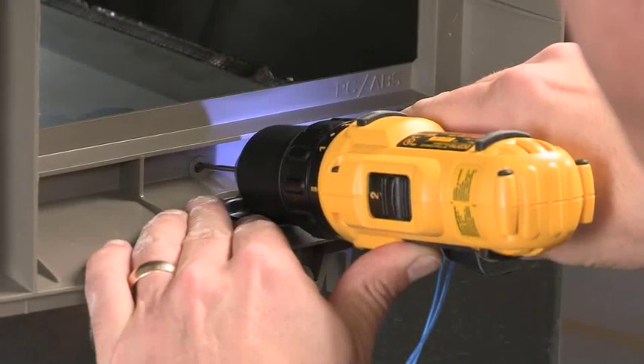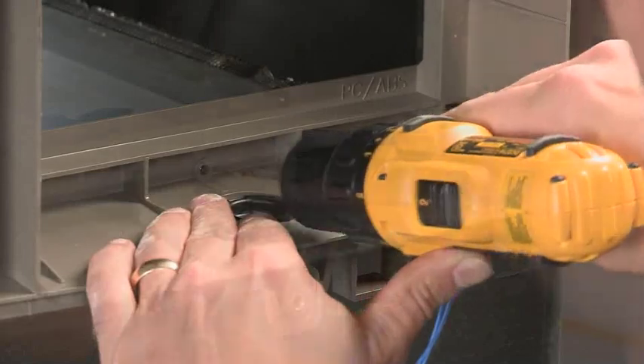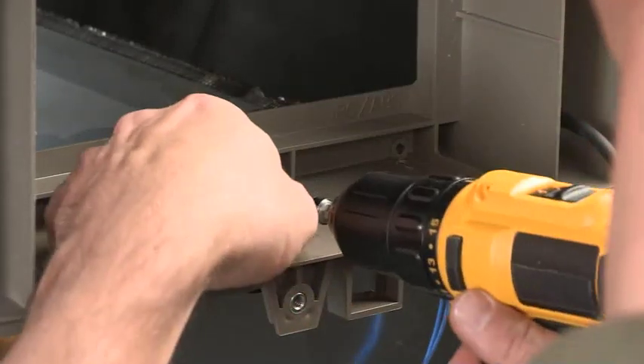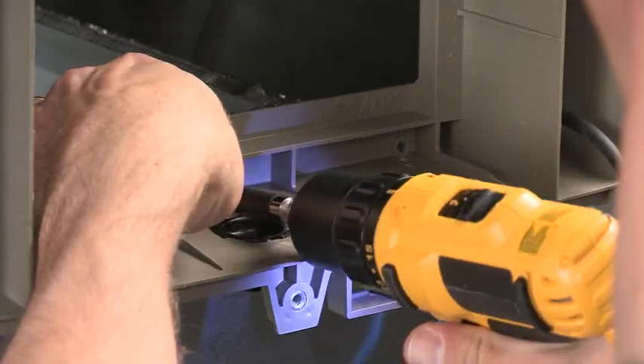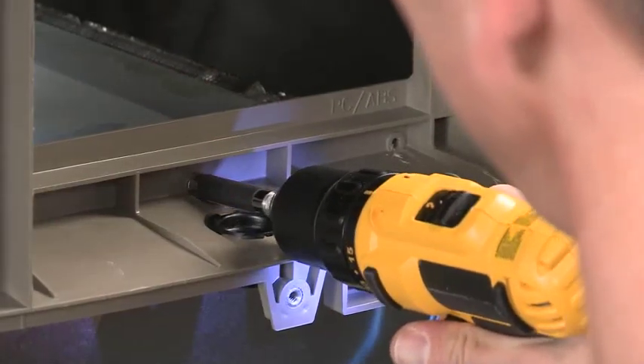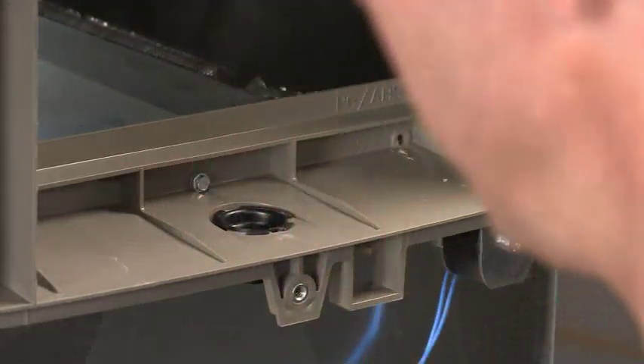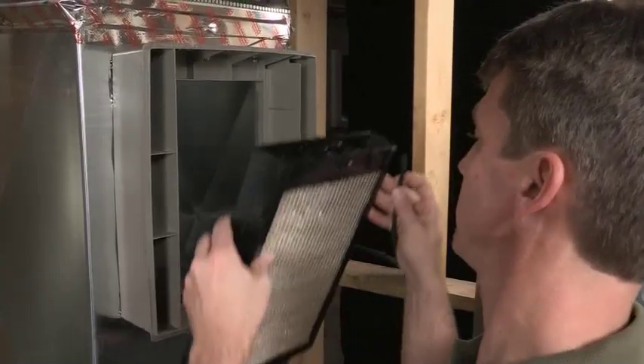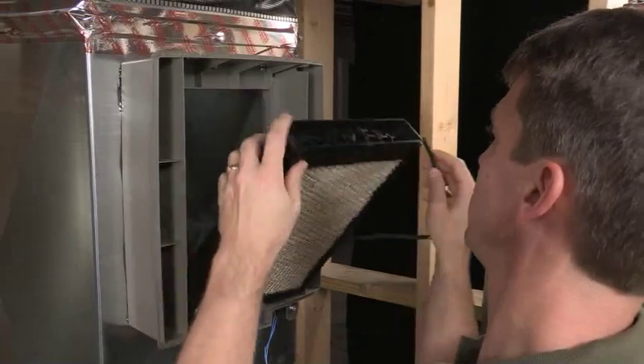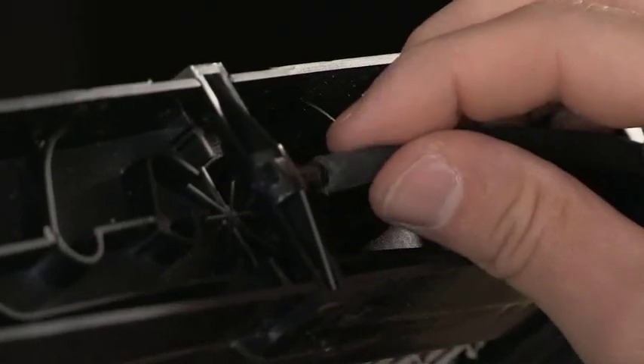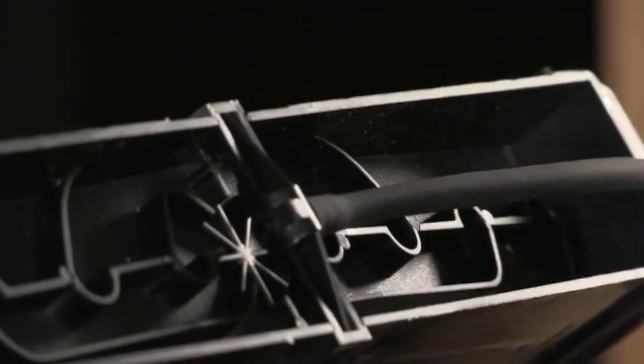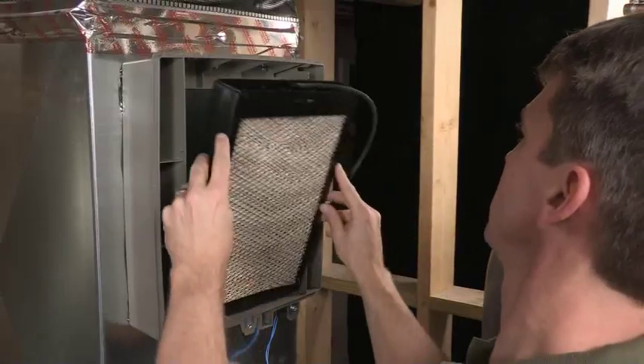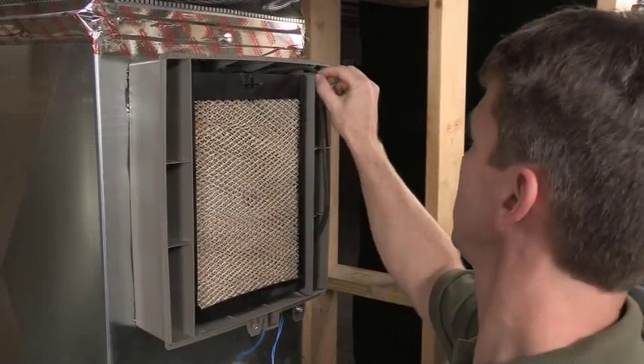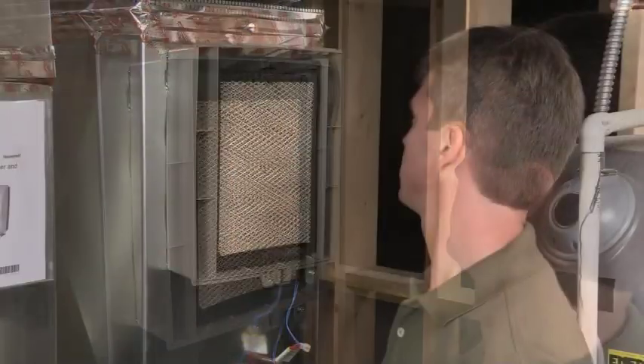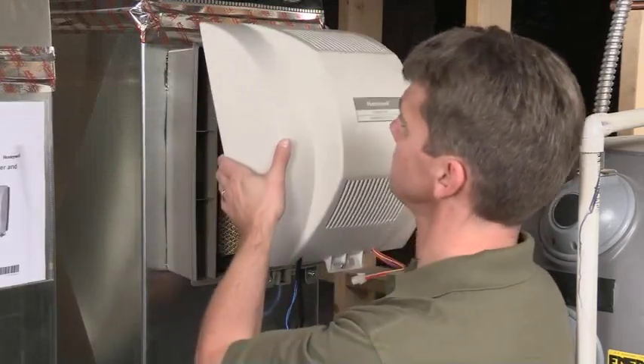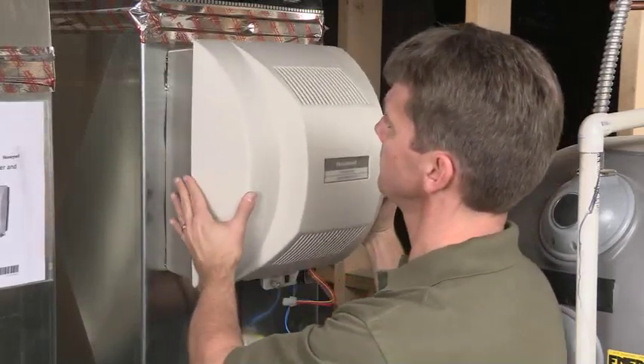Drill the holes and use the sheet metal screws provided to secure the housing in place at the top and bottom of the opening. Note that pressure may need to be applied for the screws to get through the sheet metal. Reinstall the humidifier pad in the humidifier housing. Be sure to reconnect the water feed tube at the top of the pad frame and position along the right inside edge of the housing so the tube isn't pinched or kinked. Hinge the cover in place and secure with the thumb screw located at the bottom of the cover.